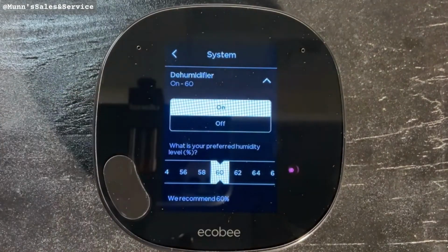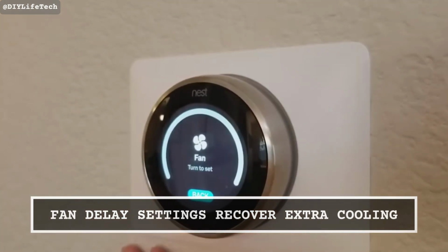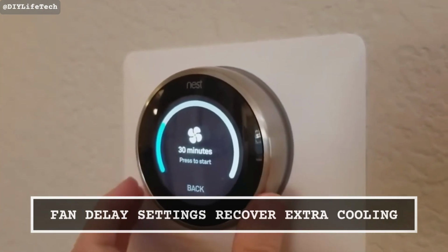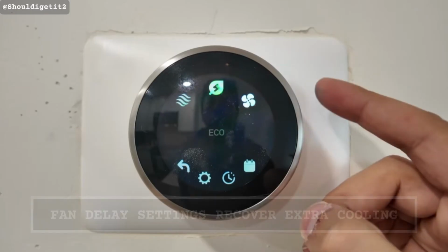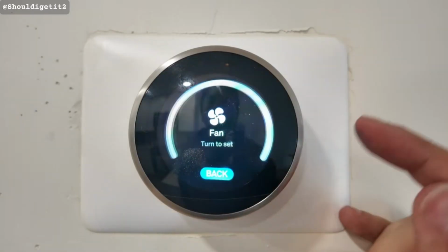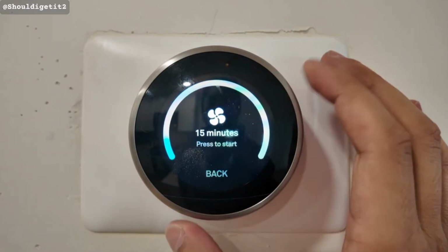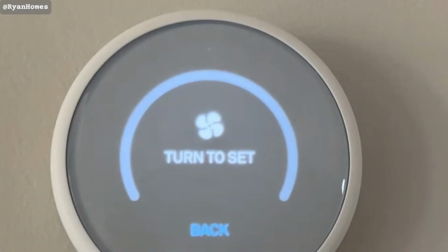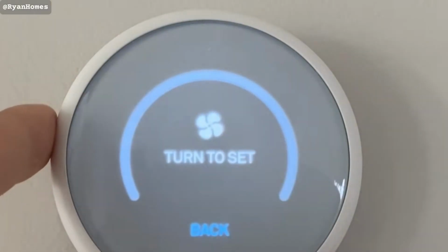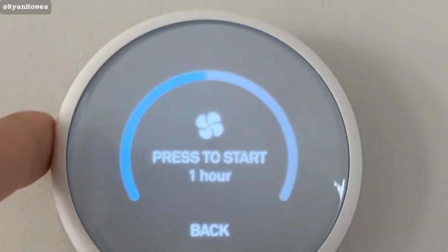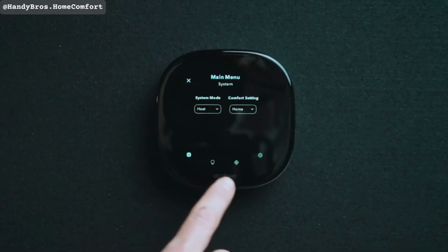Number 24. The fan-only delay setting on a smart thermostat keeps the blower running after the compressor shuts down to recover cooling left in the cold coil. Default is usually 0 seconds. Set it to 60 to 90 seconds and you capture 5 to 8% more cooling per cycle, free. Look for the setting under Installer or Advanced Menu Options.